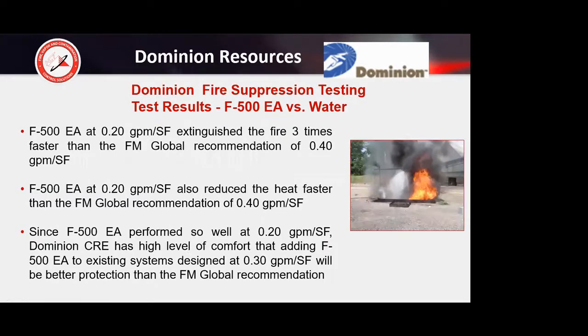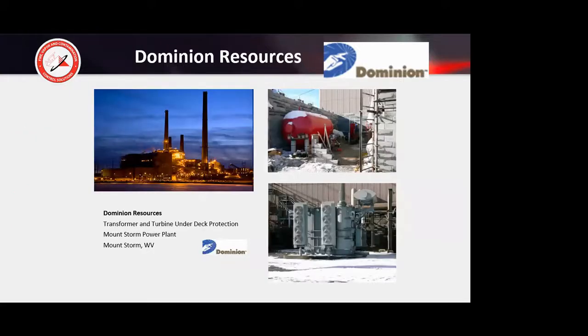So the key conclusions here were at 0.2, extinguished 3 times faster than the FM Global recommendation of 0.4. 0.2 reduced the heat faster than the plain water at 0.4, and since it performed so well at 0.20, they have a very high comfort level that adding F500 to the existing systems that are already designed at 0.3 would be a better form of protection than the FM Global recommendation. So they and the insurance company, the AHJ, all signed off on this, and we've done multiple projects with Dominion. This was the first one.